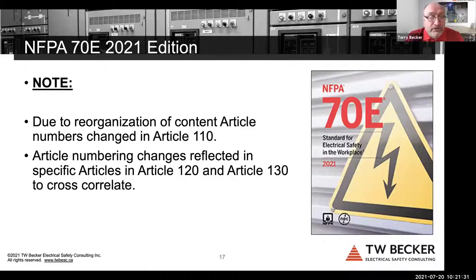Normal operating condition, we changed it in Z462 to normal equipment condition, and we moved that content from clause 4.3 or article 130, to article 110 or clause 4.1, but we put that, and there's 6 of these conditions, under the risk assessment procedure. In 70E, it's not under the risk assessment procedure. It's part of the preamble, right, related to, again, what the employer should do. And in my opinion, 70E should move that, and we might see that in the 2024 edition, under the risk assessment procedure, because normal equipment conditions need to be evaluated as part of the risk assessment procedure. And in real time, right, validated by the qualified electrical worker or the task qualified worker that's exposed.